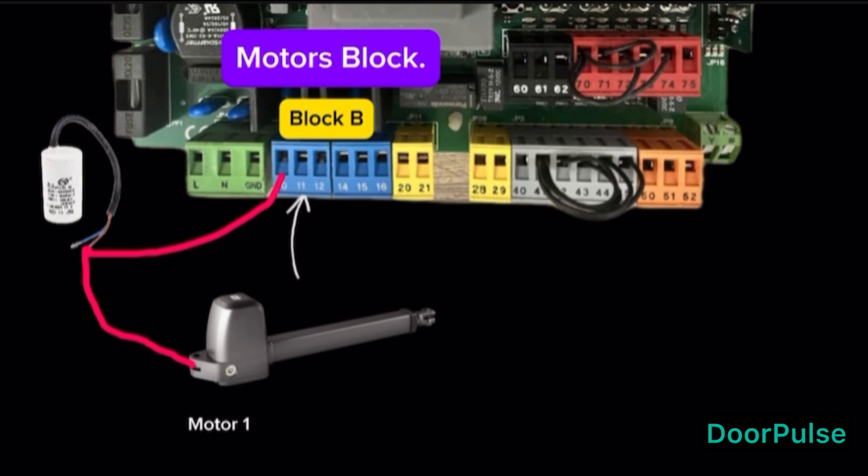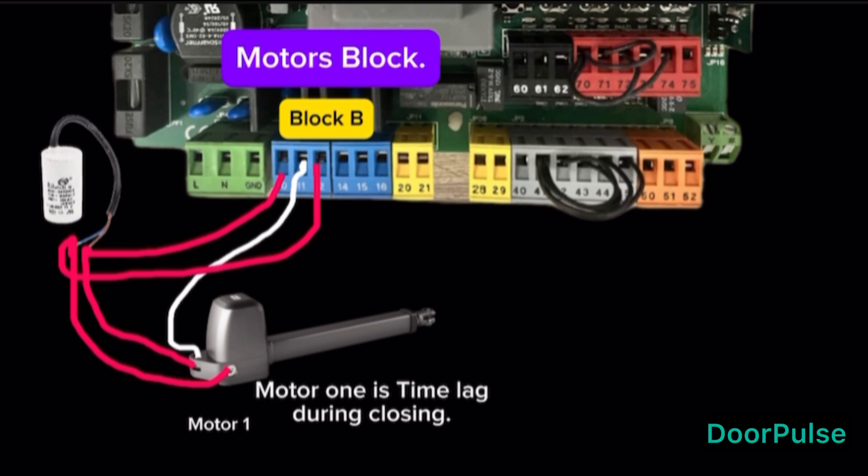Terminal 11, connect Motor 1 common wire only. Terminal 12, connect Motor 1 phase wire with condenser. Motor 1 is time lag during closing. The delay can be adjusted with Trimmer T4.